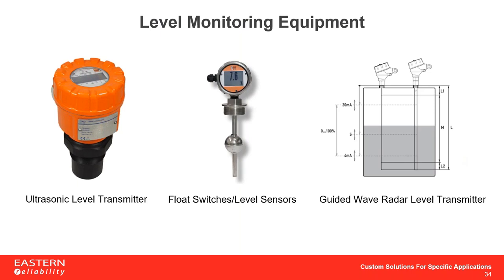For level monitoring that ties into an electrical system or SCADA system, Eastern Reliability can offer the ultrasonic level transmitter. These are typically used for more hazardous or aggressive chemicals where you don't want any equipment touching the chemical itself. If you have a less aggressive chemical compatible with stainless steel, you can use a float switch — a ball that rides up and down a rod going into the tank. All of these pieces of equipment can provide a 4-20 milliamp signal so you can tie them into your system.